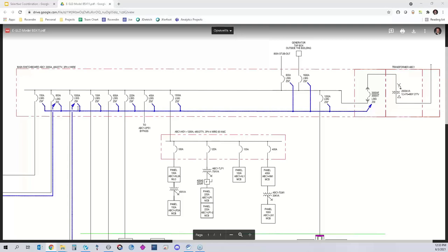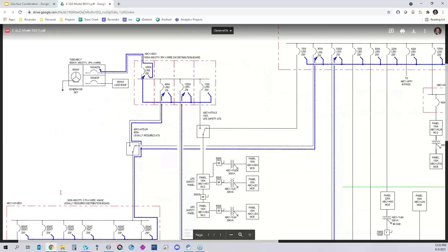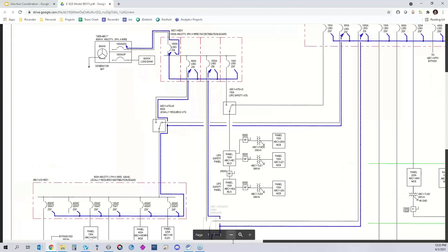Sometimes on some of these smaller frame breakers, if you put a 10, 12, or 15 times multiplier on that breaker, the maximum that that will trip at would be 15,000 amps. With a high instantaneous override breaker, you can actually turn the instantaneous off and the breaker will still have an instantaneous trip, typically up around 50,000 amps if it's a 65 K IC rated breaker. So it still complies with the UL 489 requirement, but it gives us a greater degree of selective coordination. So what this system here shows is sort of a ZSI pathway. If you slide to the left there a little bit, and we can follow over to the legally required and emergency life safety systems.